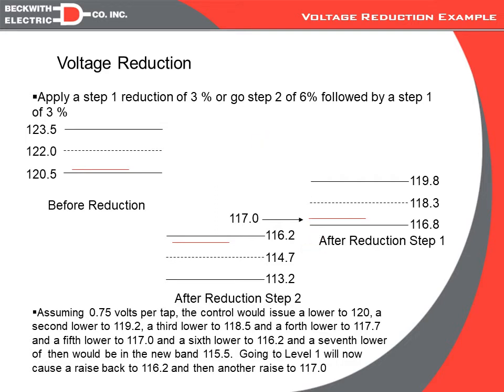So interestingly enough, if we just started with level 3, we were coming down, so we finished up at 119.2 because we're entering from the top of the band. If we start with the levels 2, 3, 6%, and then come back to level 1, 3%, now we're coming in from the bottom of the band, so to get back in the band, we're entering at the bottom, and it's 117. So even though it's a net 3% reduction in either case, we've picked up an additional 2.2 volts from 119.2 to 117 in reduction by going to the lower step first.